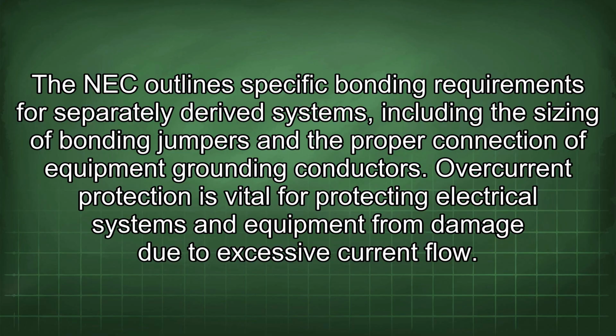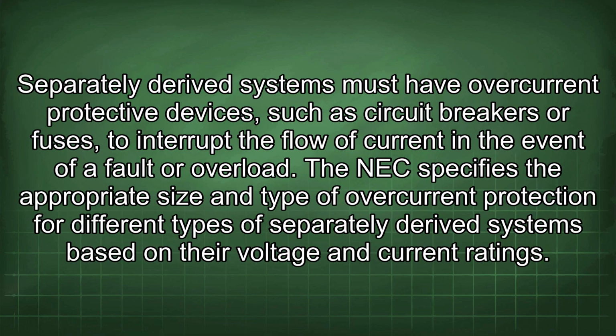of equipment grounding conductors. Overcurrent protection is vital for protecting electrical systems and equipment from damage due to excessive current flow. Separately derived systems must have overcurrent protective devices, such as circuit breakers or fuses, to interrupt the flow of current in the event of a fault or overload. The NEC specifies the appropriate size and type of overcurrent protection for different types of separately derived systems based on their voltage and current ratings.